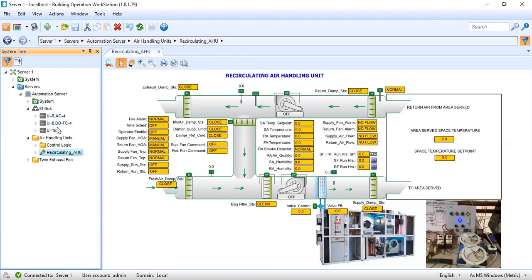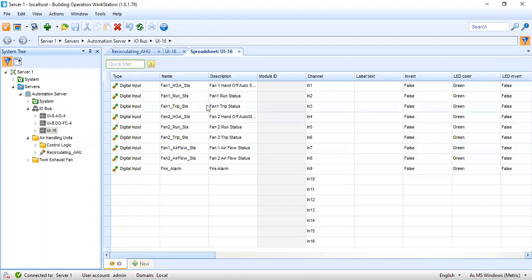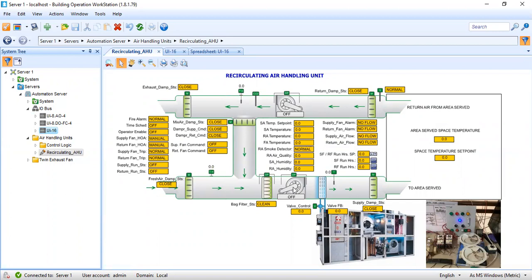The IO modules are where you will define the points in your motor control — points like hand/off/auto status, run and trip. In my previous tutorial, I already defined these points. Let me open it in a new window and edit it in the spreadsheet to show you the points defined before. I have around nine points defined. Fan one hand/off/auto status — I used this in my simple motor control video tutorial. This time I'm going to use fan one for my supply fan and fan two for my return fan. Fan one will be for our supply fan and fan two will be our return fan.